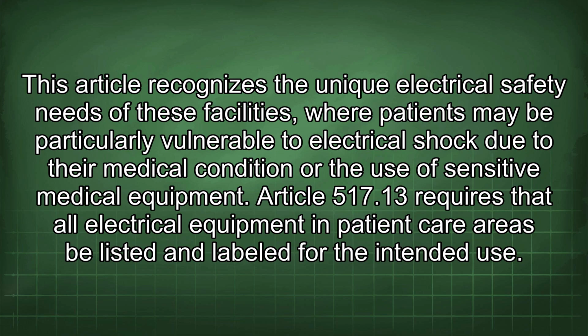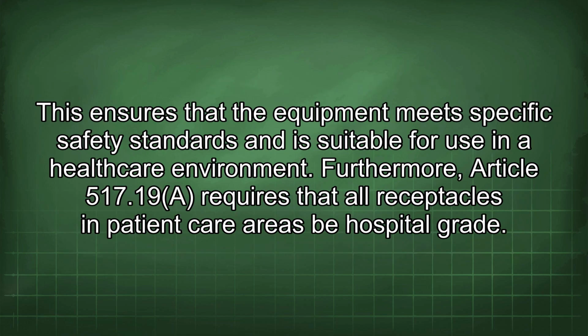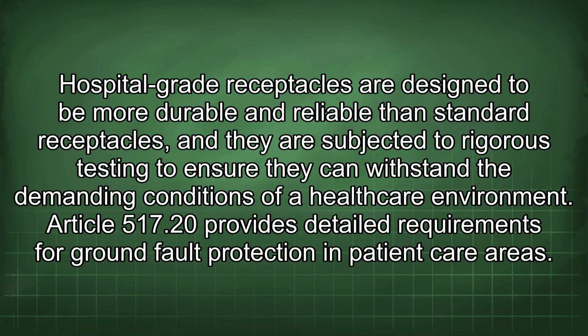Article 517.13 requires that all electrical equipment in patient care areas be listed and labeled for the intended use. This ensures that the equipment meets specific safety standards and is suitable for use in a healthcare environment. Furthermore, Article 517.19 requires that all receptacles in patient care areas be hospital-grade. Hospital-grade receptacles are designed to be more durable and reliable than standard receptacles, and they are subjected to rigorous testing to ensure they can withstand the demanding conditions of a healthcare environment.